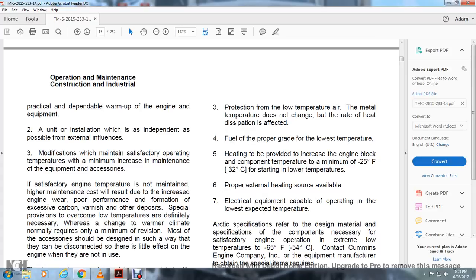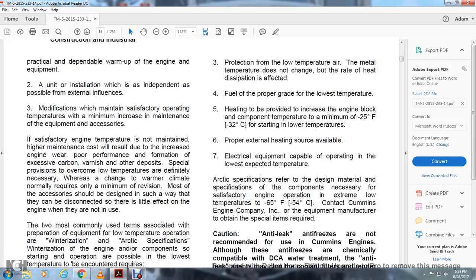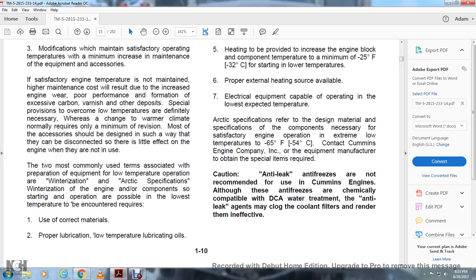Heat must be provided to increase the temperature of the engine block and components, with a minimum of negative 25 degrees Fahrenheit at start, with an external heating source available with an electrical cable for operating at the lowest expected temperatures. Arctic specification requires design, materials and components specified as necessary for the engine to start and operate satisfactorily at extreme low temperatures of negative 65 degrees Fahrenheit. Contact the engine company or the equipment manufacturer to obtain the special items required.